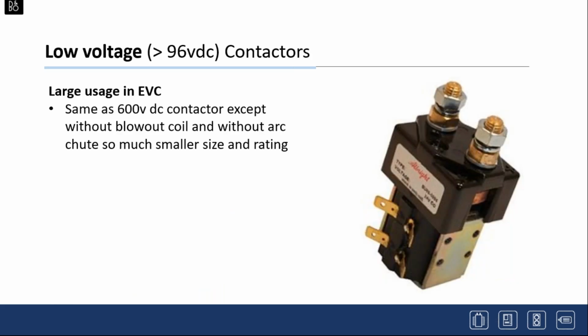Okay, I mentioned in our introduction low voltage contactors, basically anything below 96 volts, with large usage in electric vehicles. Basically, the contactor is the same as the 600 volt contactor, except it doesn't have a blowout coil or an arc chute, which are significant parts of it. So it's much smaller in size and rating. With a low voltage contactor, all you're really getting is a coil, contacts, and the terminals. So it's a much smaller device. Again, low voltage, so it doesn't have the blowout coils and the arc chutes.